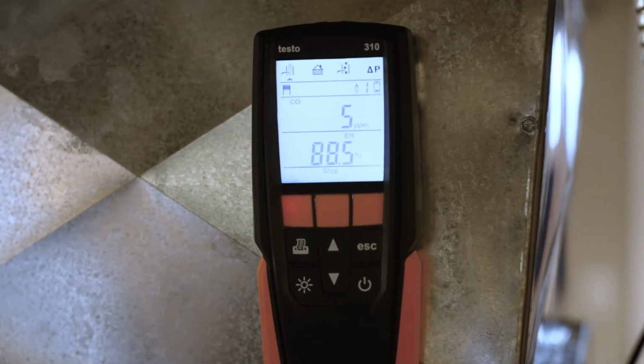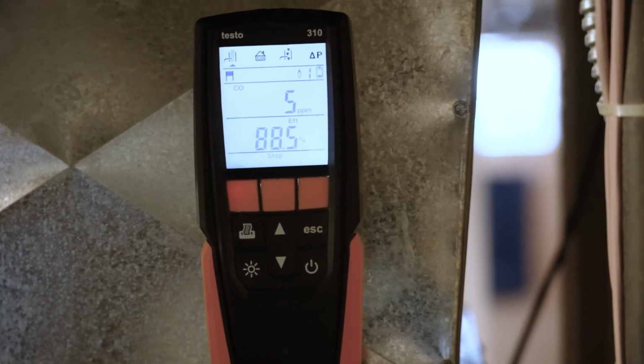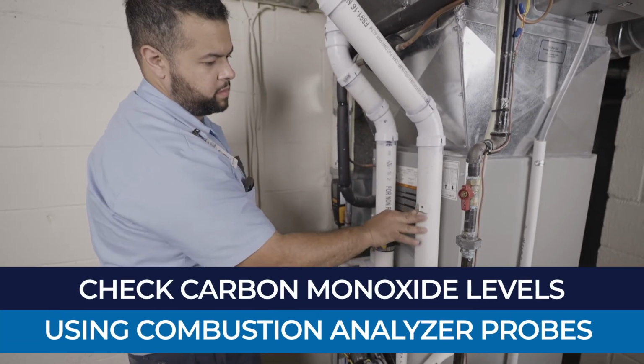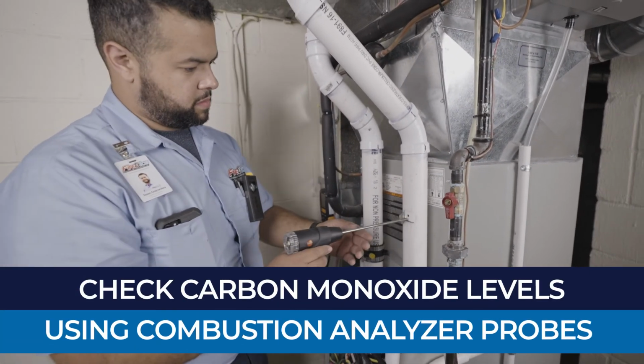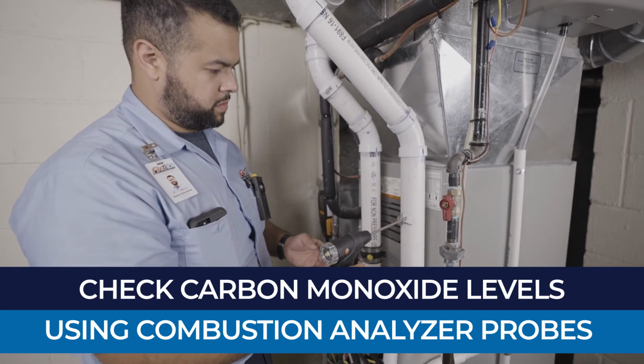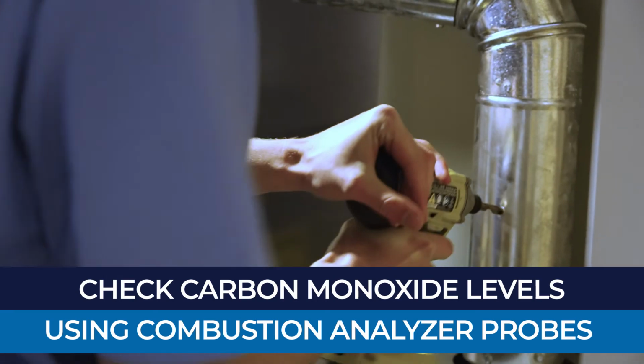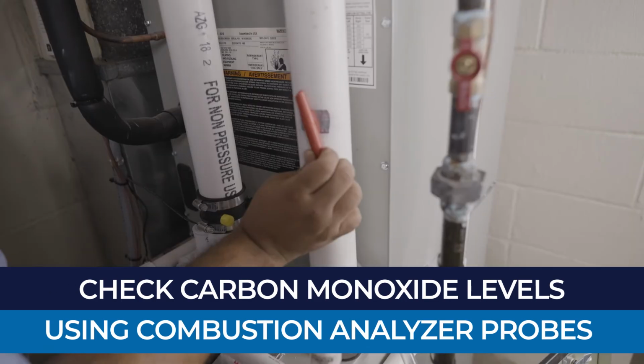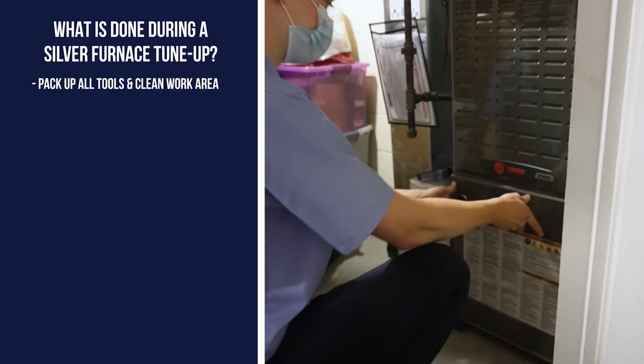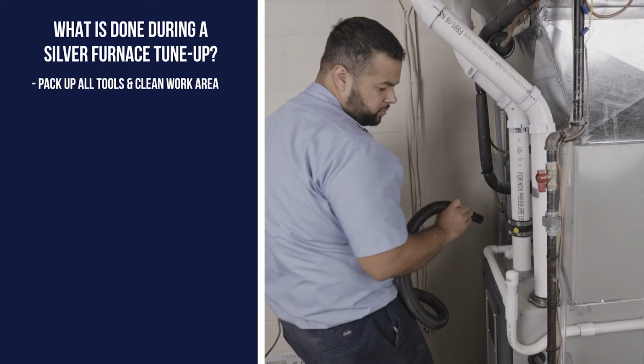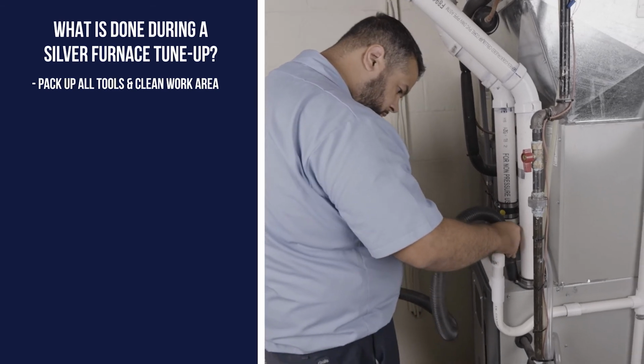One of the last but most important steps we do is to check carbon monoxide levels. We check these to ensure they are within normal levels. We perform this test by inserting a combustion analyzer in both the supply duct and the exhaust pipe through a small hole. If a hole isn't present, one will be drilled and later sealed. The last step is to put the cover back on and pack up all the tools and clean up the area we were working in.